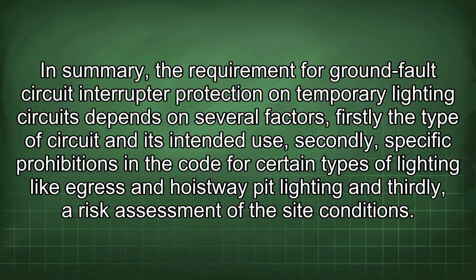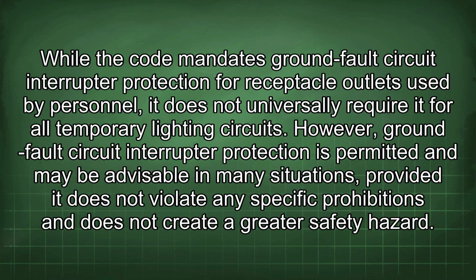In summary, the requirement for ground fault circuit interrupter protection on temporary lighting circuits depends on several factors. Firstly, the type of circuit and its intended use. Secondly, specific prohibitions in the code for certain types of lighting like egress and hoistway pit lighting, and thirdly, a risk assessment of the site conditions. While the code mandates ground fault circuit interrupter protection for receptacle outlets used by personnel, it does not universally require it for all temporary lighting circuits. However, ground fault circuit interrupter protection is permitted and may be advisable in many situations, provided it does not violate any specific prohibitions and does not create a greater safety hazard.